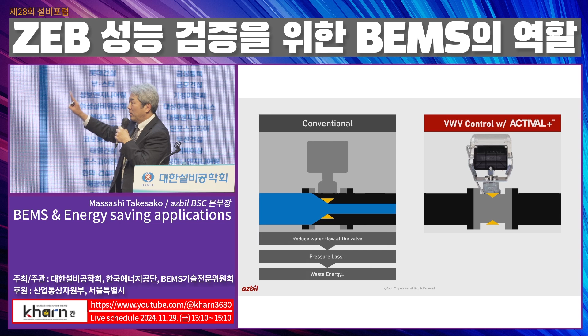We have to reduce the pump discharge pressure as low as possible. Then we can minimize the friction loss by the control valve. As a result, pump energy consumption can be reduced. This is a very basic concept also. But again, in order to achieve this, we have to think not only about the pump itself, but we also need to know how the AHU is operating. According to the AHU control condition, we get feedback from the AHU, and then finally we can optimize the pump discharge pressure. This is the entire system efficiency improvement. This is what we are saying and we are now promoting.